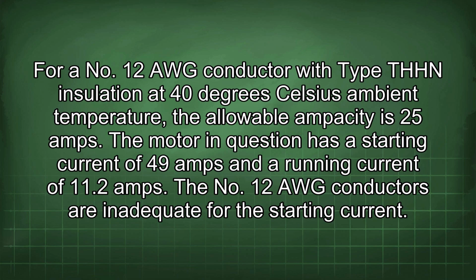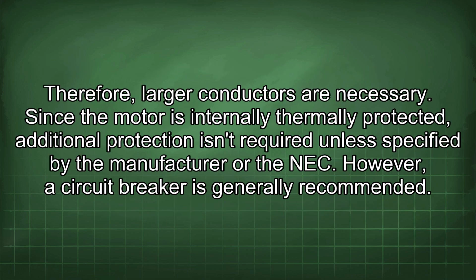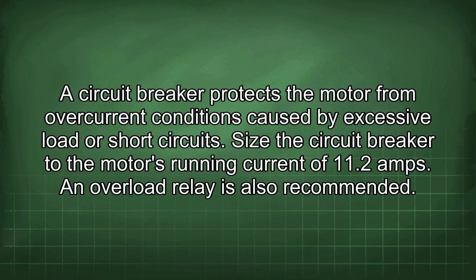The 12 AWG conductors are inadequate for the starting current. Therefore, larger conductors are necessary. Since the motor is internally thermally protected, additional protection isn't required unless specified by the manufacturer or the NEC. However, a circuit breaker is generally recommended. A circuit breaker protects the motor from overcurrent conditions caused by excessive load or short circuits.